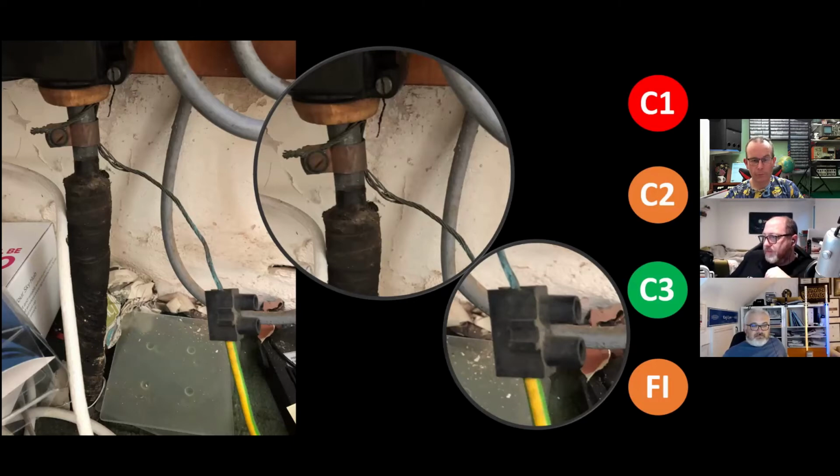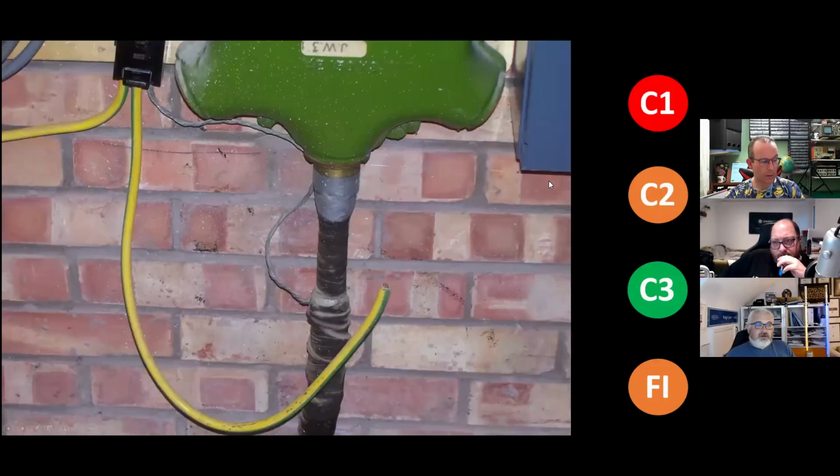Right. About 80% voted. We have got C2, 64%. Yeah, I think if you looked at 7671, could you say that the connection method is not putting the conductor under strain, given the fact that the entire installation relies upon it for safety of operational and protective devices? Yeah, we need the adequacy of that connection is definitely. If you look at the PME guide that we looked at earlier on, there are lots of references to a minimum 16 mm to connect the supply into the supply cable. And that's in a lot of the DNO PME guides now. So yeah, C2, I'll go with that definitely.